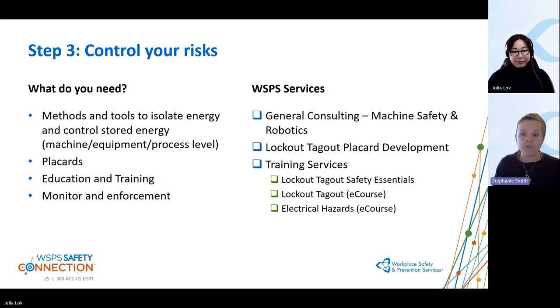When we're going through, if we see a gap—like maybe you have a pneumatic shut-off that's only a lever type, not a dump valve, so you can't bleed the line, and there's no way to verify you're in zero energy—we'll make recommendations in that placard. We recommend having a quarter-turn dump valve to ensure you can bleed off the line, and we recommend having a gauge.